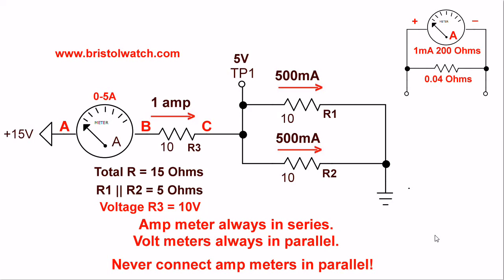First of all, you never put the meter on ohms reading to measure voltage. You don't do that. You'll probably damage the meter. You never connect an ammeter, which you have here at A and B, you never connect an ammeter in parallel to a load. Never.